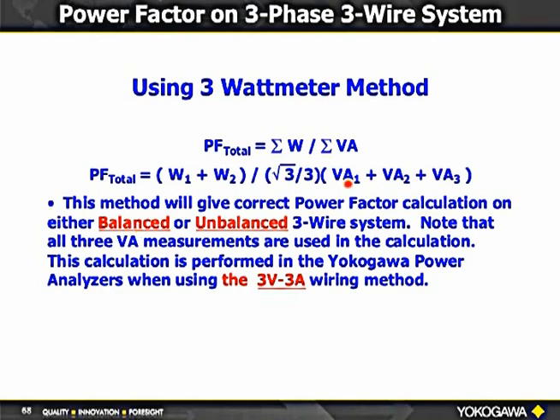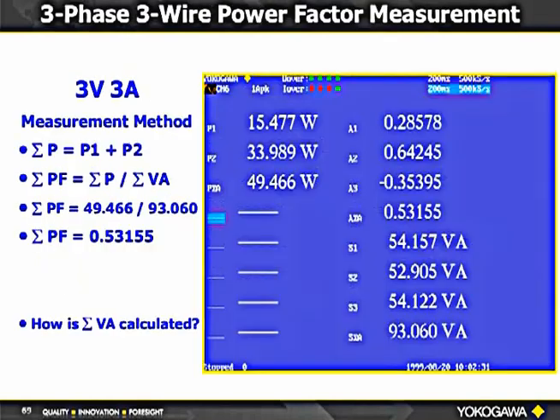Here's another example of the 3V3A measurement method with the two-wattmeter method: total power reads 49 W, total VA is 93 VA, and power factor is 0.53.